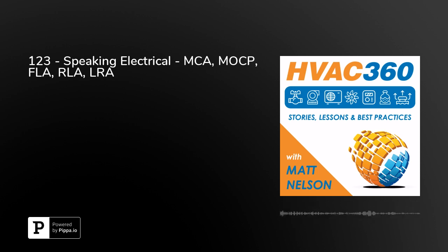So you can do that. Now the last piece is another calculation, and this is the MOCP. This is the maximum overcurrent protection. Now, you're probably thinking, Matt, that's only 3 words, maximum overcurrent protection, MOCP. You can refer to it as the MOP. That's also another acronym that's used. So the MOP and the MOCP are the same thing. I guess if you want to split overcurrent into 2 words, then it's MOCP.